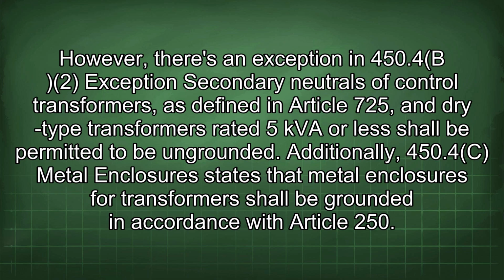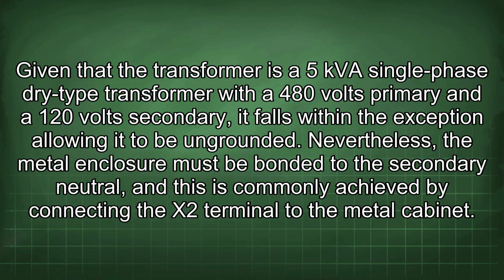Additionally, 450.4(C) metal enclosures states that metal enclosures for transformers shall be grounded in accordance with Article 250. Given that the transformer is a 5 kVA single-phase dry-type transformer with a 480 volts primary and a 120 volts secondary, it falls within the exception allowing it to be ungrounded. Nevertheless, the metal enclosure must be bonded to the secondary neutral, and this is commonly achieved by connecting the X2 terminal to the metal cabinet.